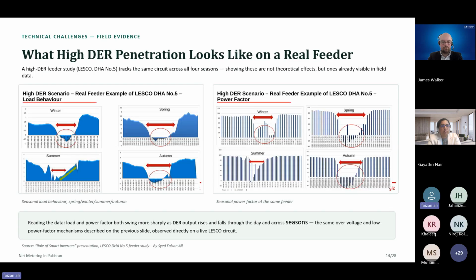So this is an extract from one of my other presentations, where we see a medium voltage feeder at one of Lahore's distribution companies. We see that during the winter, spring, autumn, and even the summer seasons, at midday there is no supply of power from the grid. Rather, there is reverse power flow. So this blue part going below the zero line is the reverse power flow.